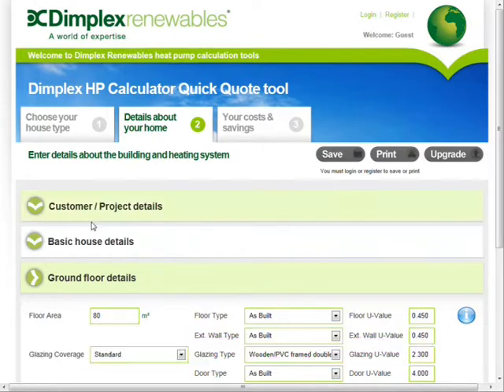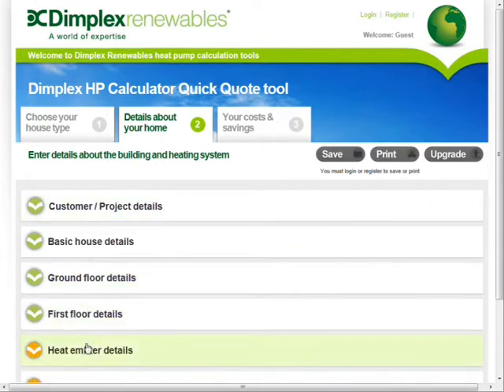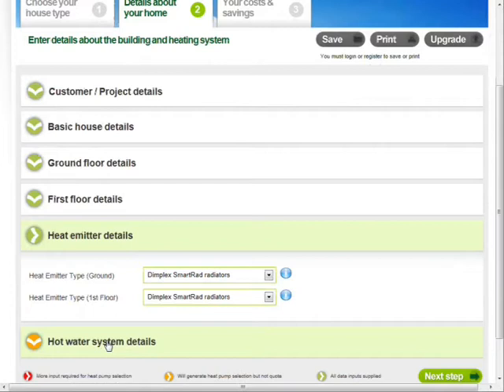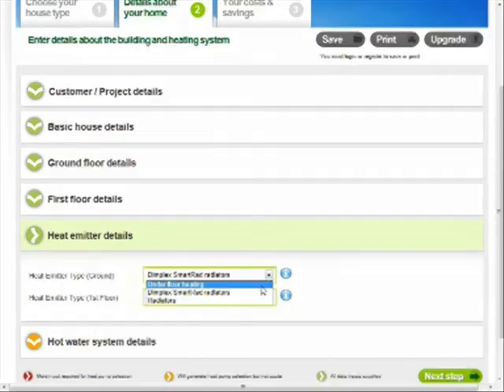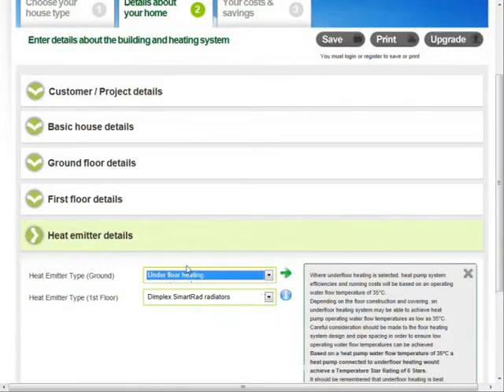The values entered for the ground floor are automatically entered for the second floor, although these can be adjusted if necessary. There is a choice of three heat emitters: either underfloor, smart rads or standard radiators. Each of the heat emitters has a flow temperature of 35, 45 or 55 degrees respectively, which will affect the expected SPF of the system.